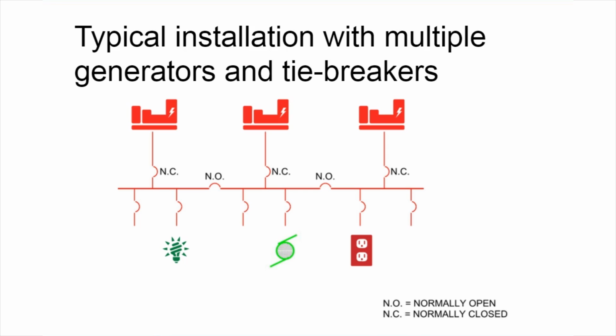So what else can we do with the emergency system? Here's an example of where we've got multiple generators tied to multiple buses, which are all then tied together with normally open breakers. And these could be automatic or these could be manual. In most cases, they'd be manual. Here, you could look at putting all your life safety loads on one of these buses, served off of a single generator so that they're all picked up in their block load.